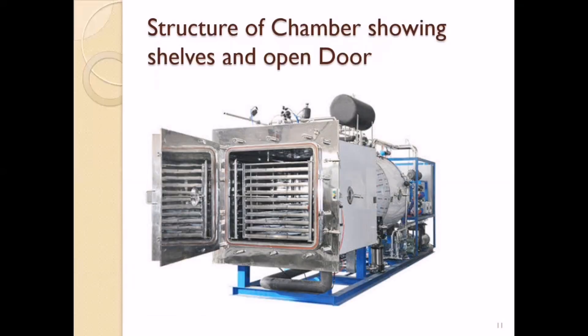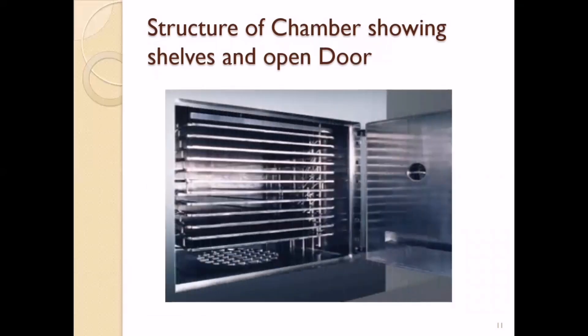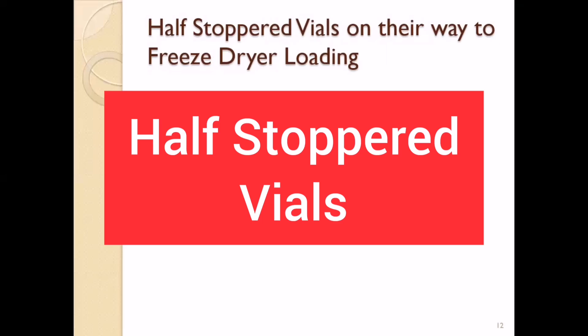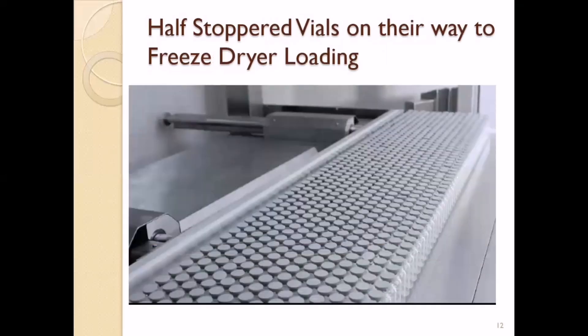Now let's understand the structure of the chamber. This is a basic rectangle chamber structure with shelves inside — this is how the freeze-dryer chamber looks from inside when the door is open. The half-stoppered vials are filled and arranged onto the shelf, and then with one push they go into the chamber area onto the shelf.